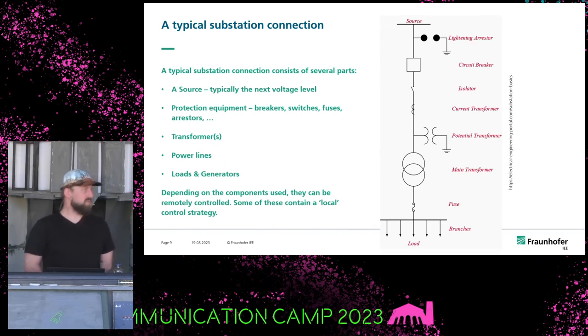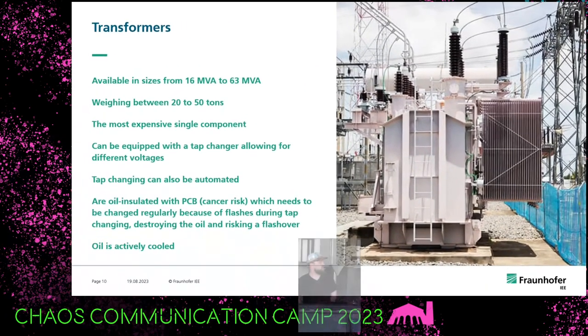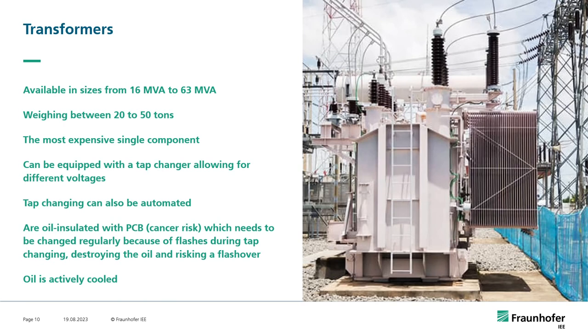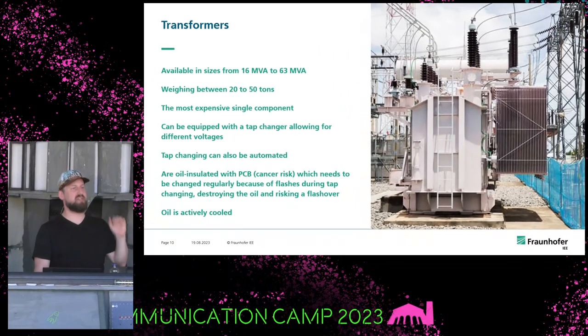Some of these components are controlled and are remotely controllable. For example, transformers are normally these big heavy blocks which take a lot of power and transform it down, and they can have a changeable tap, which means you can change how much voltage they produce by changing which winding you are using to transform the power down. This part is automated in the high voltage grids. In the low voltage grids this is normally not automated, but we are at the moment trying to automate these things. Also, most of the time they have a local controller which keeps track of the local voltage and changes the taps accordingly.